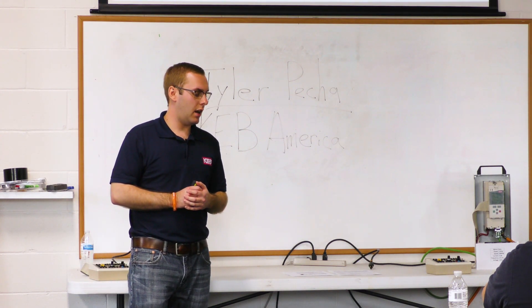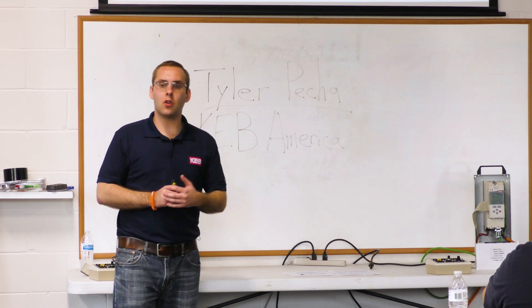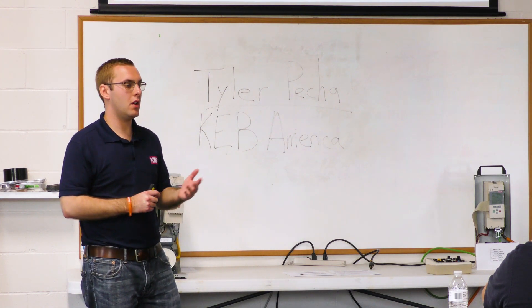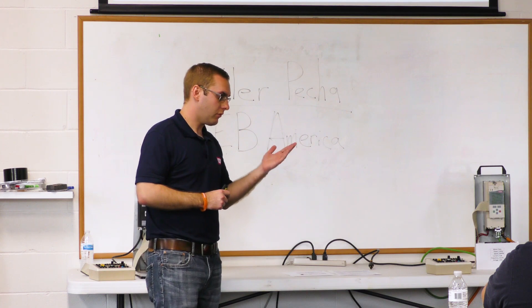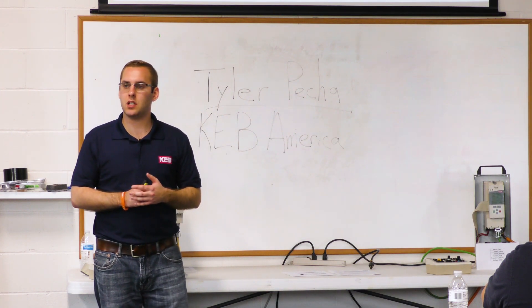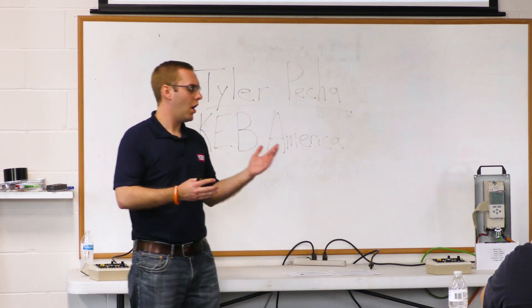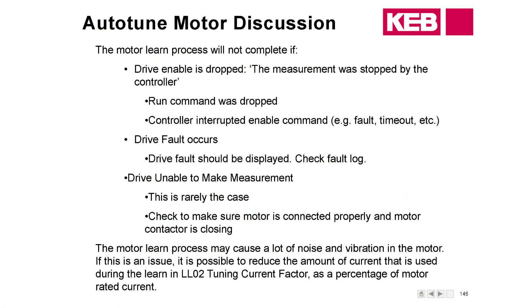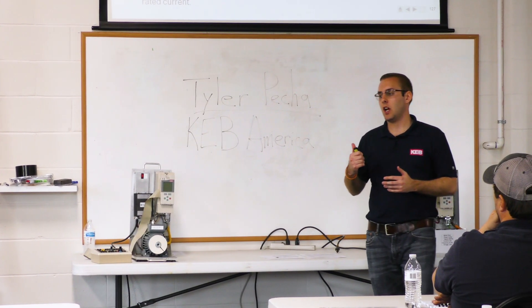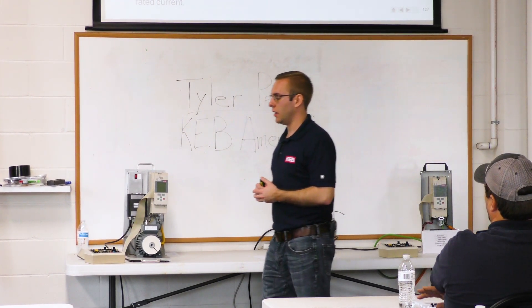You might get an encoder 1 fault if you have an induction machine. That would be due to missing the channel pairs on the encoder. You also may get a controller error or a drive enable switch-off event. If you drop the enable, the autotune will stop right there, so check the controller and make sure it's not faulting.